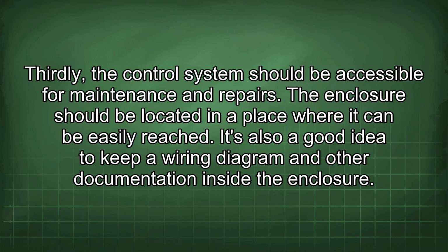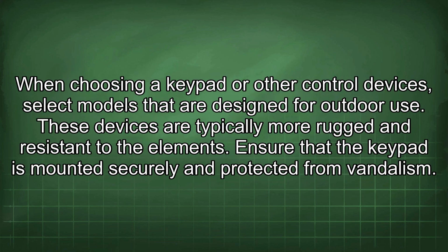Thirdly, the control system should be accessible for maintenance and repairs. The enclosure should be located in a place where it can be easily reached. It's also a good idea to keep a wiring diagram and other documentation inside the enclosure. When choosing a keypad or other control devices, select models that are designed for outdoor use. These devices are typically more rugged and resistant to the elements. Ensure that the keypad is mounted securely and protected from vandalism.